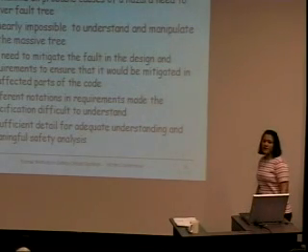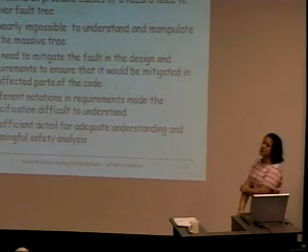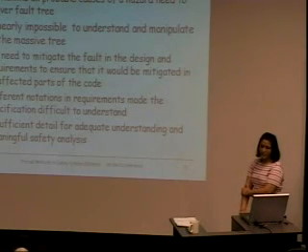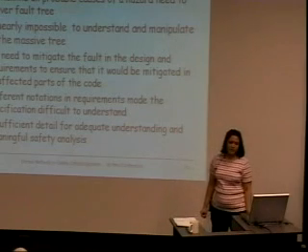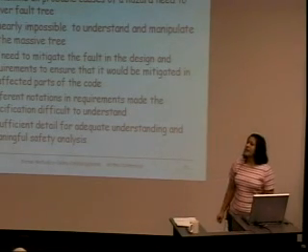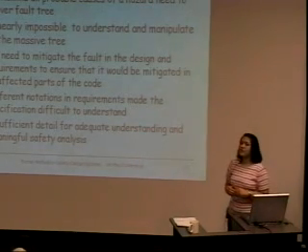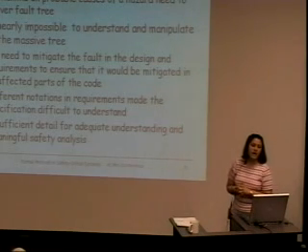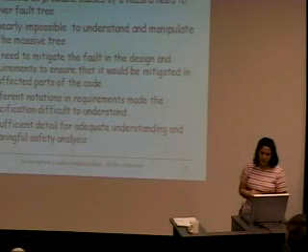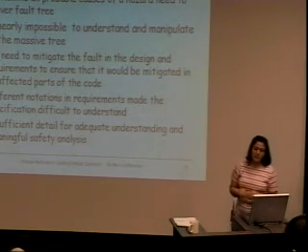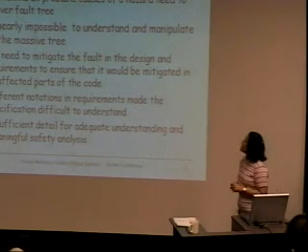So why is the software safety analysis in defibrillators difficult? First of all, we can't go over the code line by line to find the faults. And even for these kinds of devices which are highly safety critical, the fault tree is very huge and it is a massive tree. So it's nearly impossible to understand the whole fault tree.